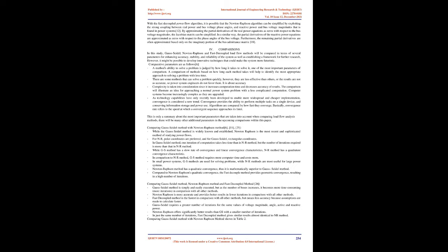Accordingly, the method to be selected is dependent upon the overall costs involved in solving load flow issues as well as response time and accuracy. In the fast decoupled power flow method, lines are assumed to be extremely inductive, i.e., the R/X ratio is quite low. Since these assumptions are taken into account, the fast decoupled power flow method creates constant matrices that are used during all iterations and only need to be factorized once. In cases where this assumption is flawed, e.g. in distribution networks and certain sub-transmission networks, the convergence for this method may be slow or may not take place at all. To handle such a problem, it has been proposed to use an axis rotation method by rotating both the bus admittances and the complex power injections using a unit magnitude complex scalar factor. Fast decoupled power flow method can be improved with an optimal selection of this factor, as this complex factor modifies the R/X ratio of lines.